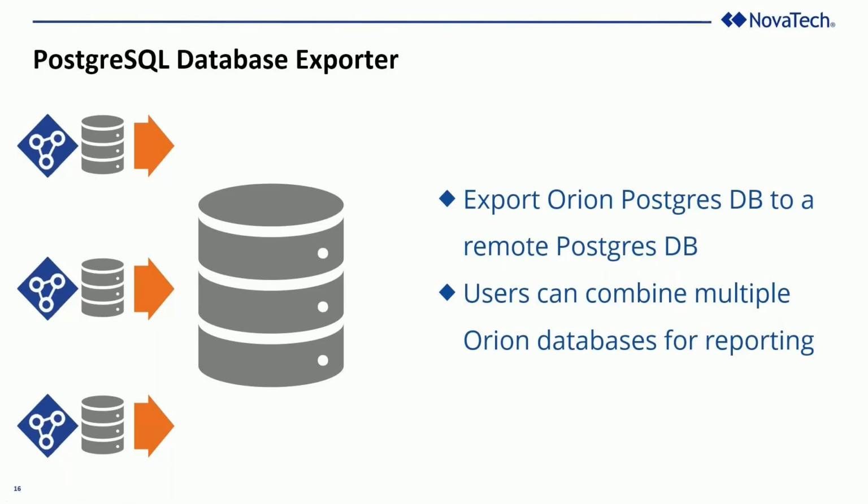This enables you to have permanent offsite storage access of the database records, which is, I think, vital in today's world. You can have a centralized sequence of events database and a centralized archive of everything that's going on in the substation using it. It will transfer both the archive for the analogs and also the alarm archive. So if you've got binary or analog alarms, it will save those as well.